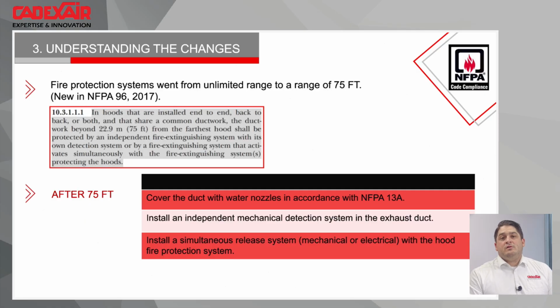So now we have three options. The first one, you go as per NFPA 13, so you will put a sprinkler inside of the ductwork. And that could be some issue. If the duct is outside, you need to have a special sprinkler or something like that. After that, if you have an independent mechanical detection system in the exhaust ductwork, we can use the same one we use in the kitchen exhaust hood. So we put a fusible link, a fire protection system, and the nozzle, so it will shoot there as soon as the fusible link melts at the rated temperature. And the other one, we can use what we call a simultaneous release system. So we can hook it up the mechanical way or the electrical way with the system in the kitchen, and it shoots at the same time as the one inside of the kitchen.